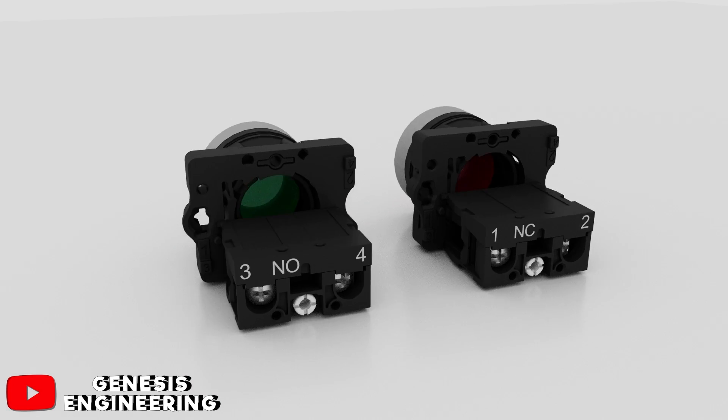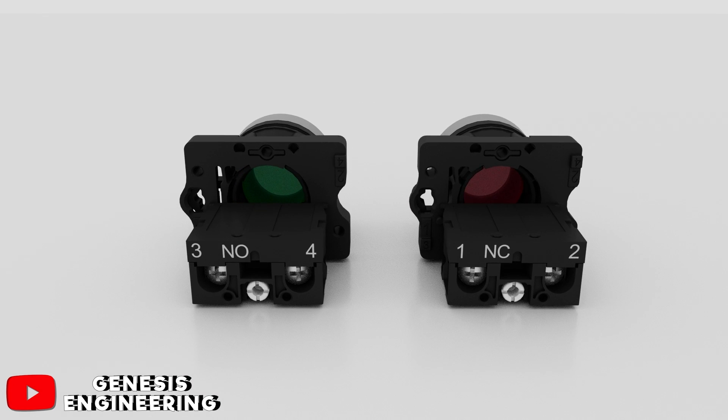These buttons are not just the colors that are different, the contacts too. The green button to start the motor has the normally open N.O. contact, working as follows: without power the contact is open and when the button is pressed the contact will close and the motor will start. The normally open green button has terminals 3 and 4, where 3 is the input and 4 is the output.